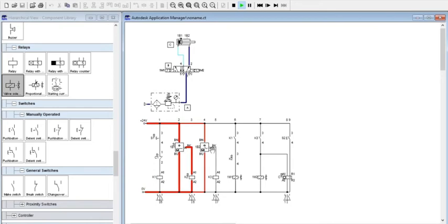When it changes to normally closed, electrical flow goes through the coil of relay K3 and it will energize. So switch K3 also changes from normally open to normally closed, and solenoid 1M2 also will energize. It also helps the extend and retract movement of the cylinder.